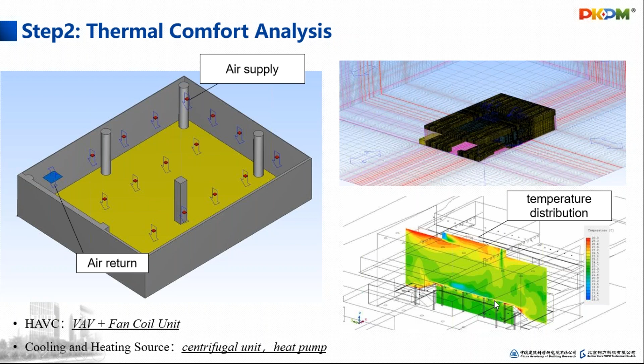So we made a suggestion to the HVAC design. First, we added mechanical air exhaust devices at the ceiling to accelerate the exhaust of hot air at the top. Then we changed the location of the air returning device. In the original design it was at the ceiling, so hot air returned from the top. Now we put it at the side walls, installed at a lower position, so hot air would return from the side.